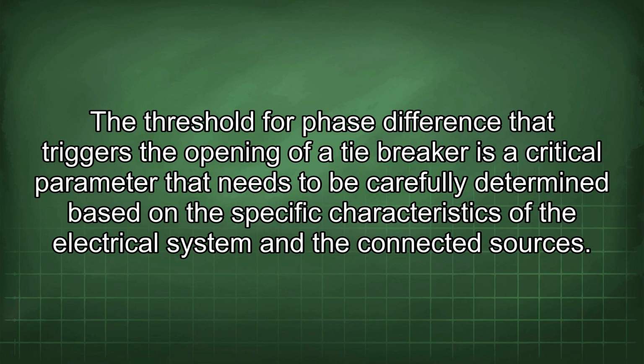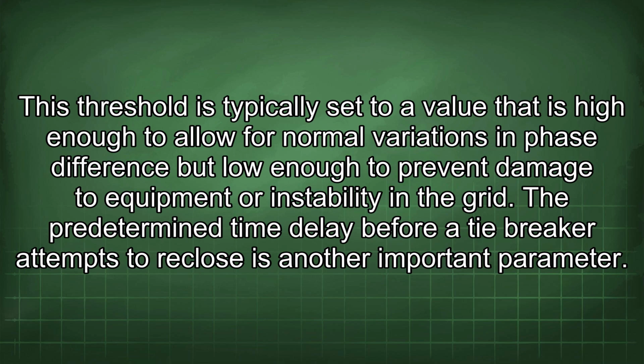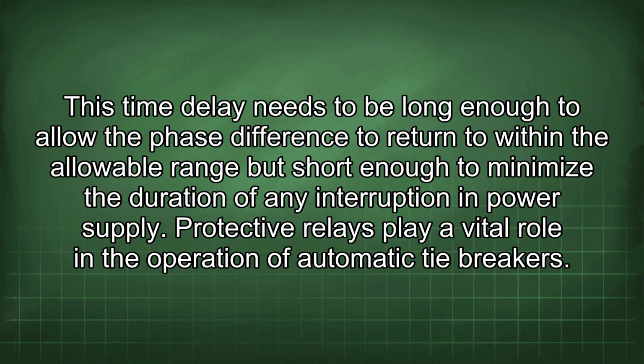The threshold for phase difference that triggers the opening of a tie breaker is a critical parameter that needs to be carefully determined based on the specific characteristics of the electrical system and the connected sources. This threshold is typically set to a value that is high enough to allow for normal variations in phase difference, but low enough to prevent damage to equipment or instability in the grid. The predetermined time delay before a tie breaker attempts to reclose is another important parameter. This time delay needs to be long enough to allow the phase difference to return to within the allowable range, but short enough to minimize the duration of any interruption in power supply.